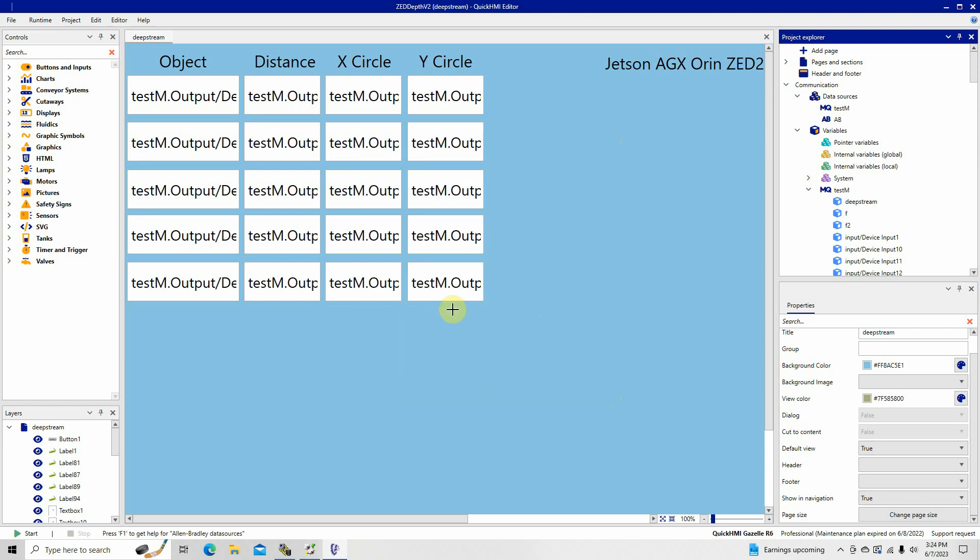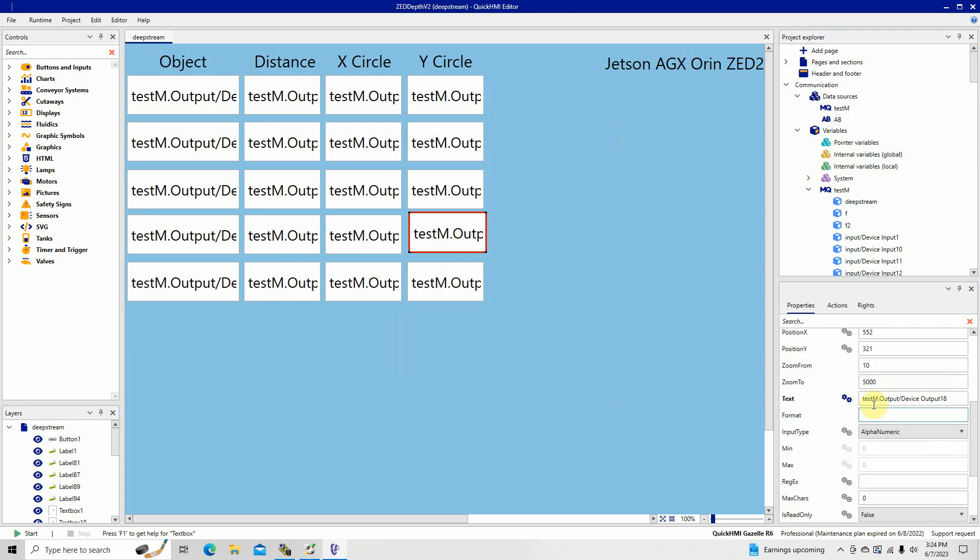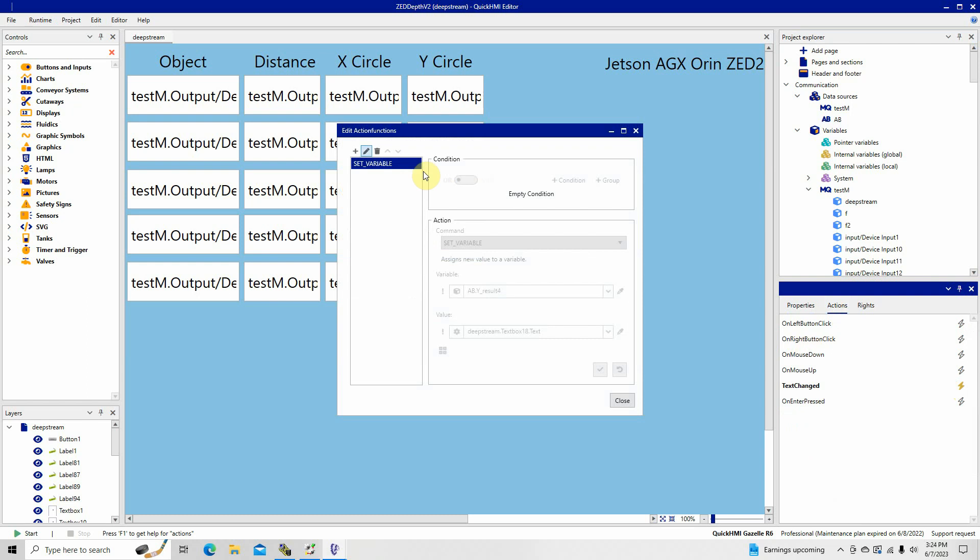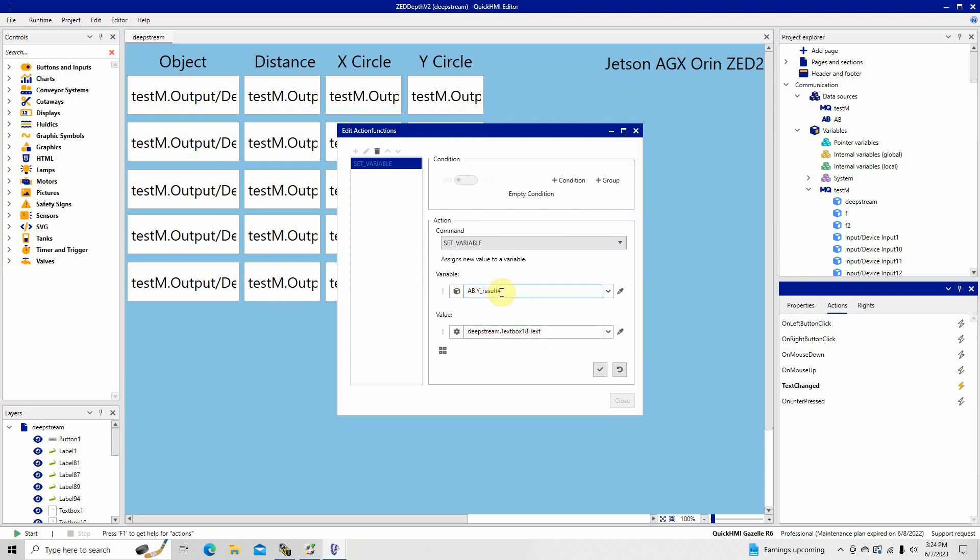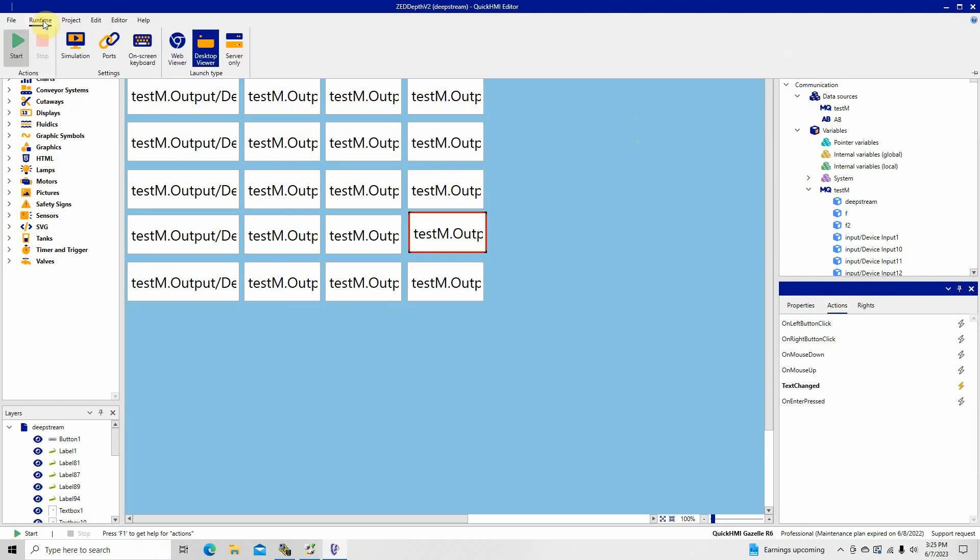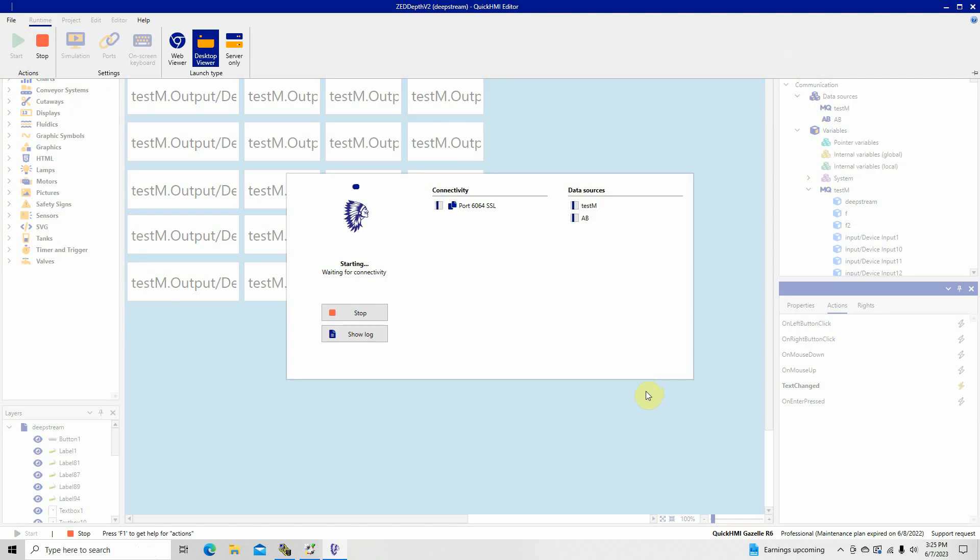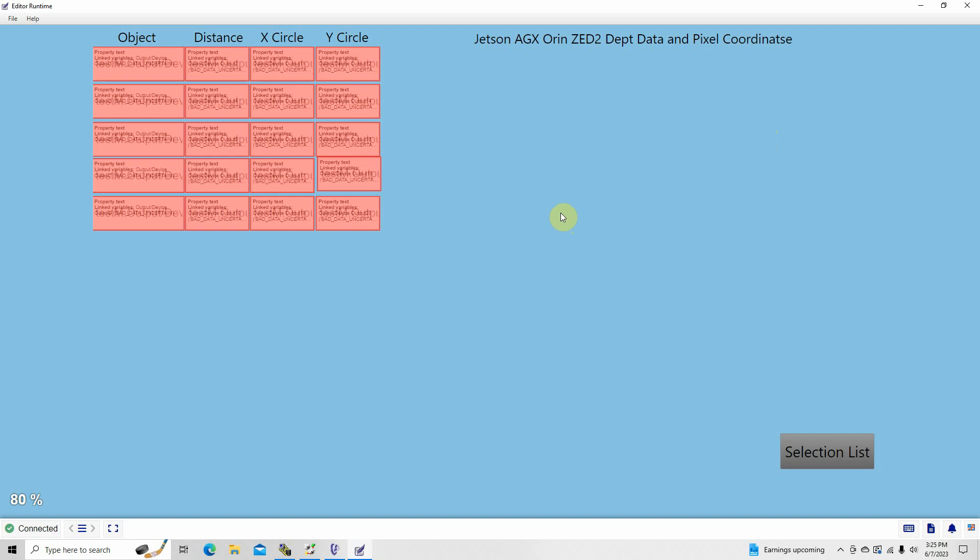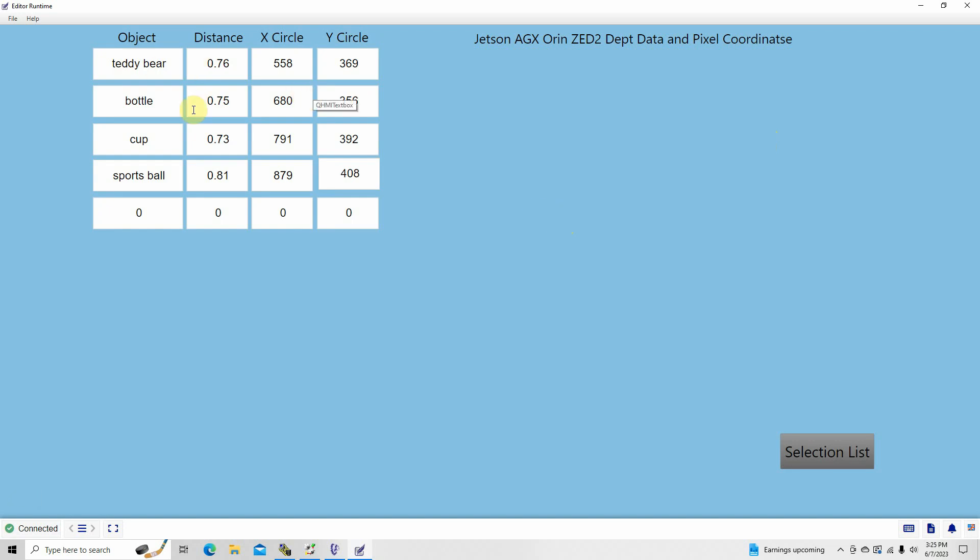For example, right here, this is the test output device. This is the information that's being extracted from the MQTT server and being displayed. If you go to actions here, it takes that and sends it right back out. This is the tag that goes to the Allen Bradley Control Logix right here. So it takes the text in this text box and sends it to this tag immediately. You can see right here, I can run this from here.